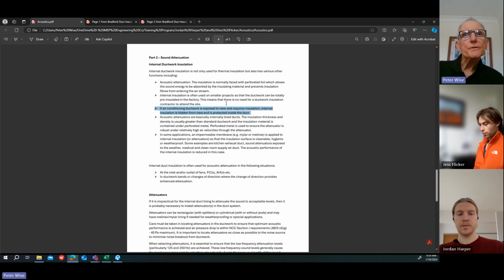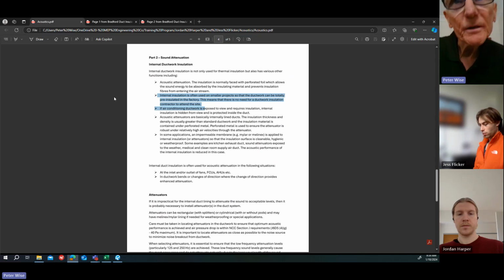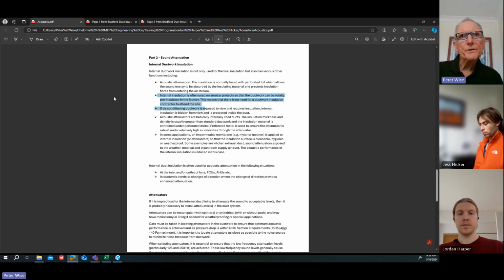Sorry, just on that one, that's worth remembering. Some contractors may prefer on a small project just to use all internal insulation because it's easier on site. All the ductwork is delivered to site, pre-insulated. All they have to do is install it on site. They don't have to get another contractor to come in and apply the insulation. If air conditioning ductwork is exposed to view and requires insulation, internal insulation is hidden from view and protected inside the duct.